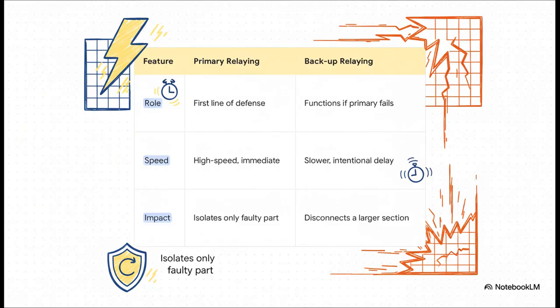Think of it this way. Primary relaying is the first responder on the scene. It's super fast and super precise. But if it fails for any reason, a bad sensor, a dead battery, who knows, the backup system kicks in. Now, the backup is intentionally slower. It gives the primary system a chance to do its job first. But if it has to act, its impact is bigger. It'll disconnect a larger section of the grid just to be absolutely sure the fault is cleared. It's a trade-off. A slightly larger outage is way better than a catastrophic grid failure.